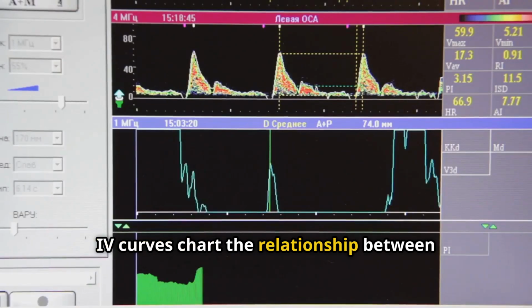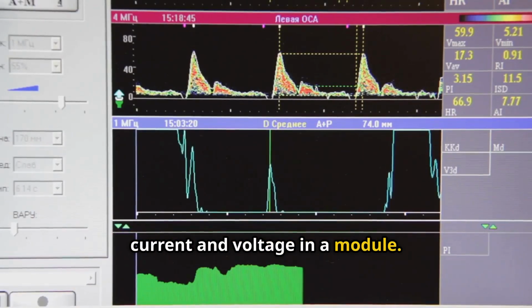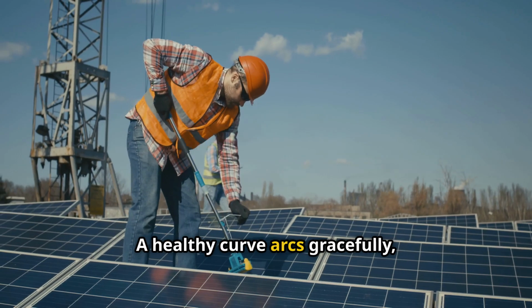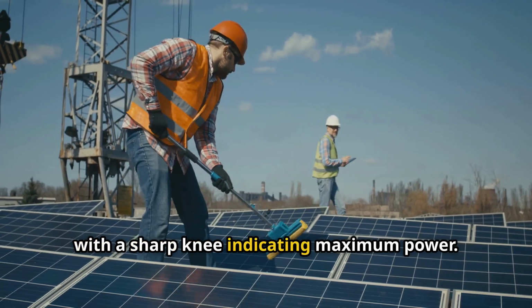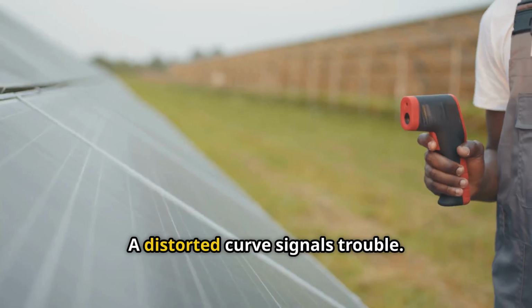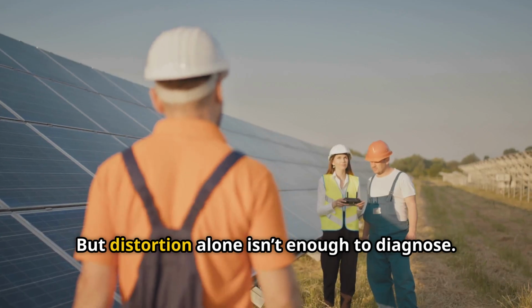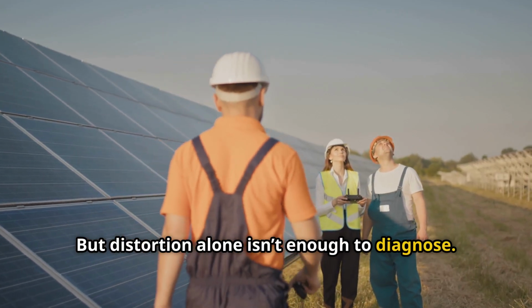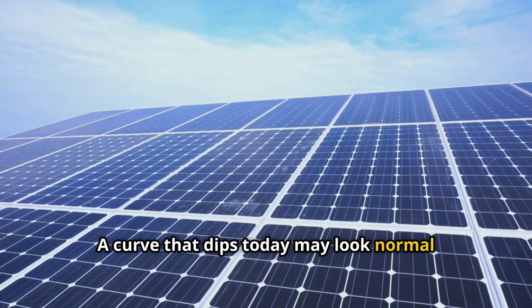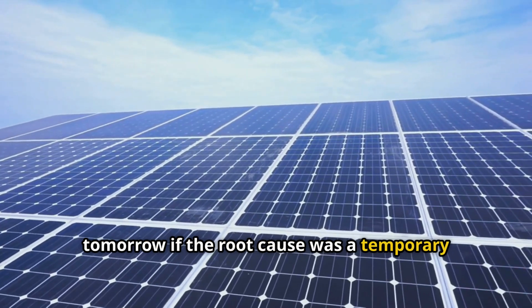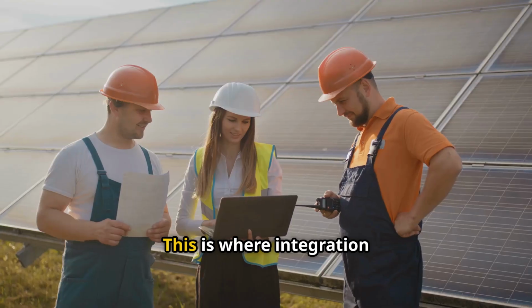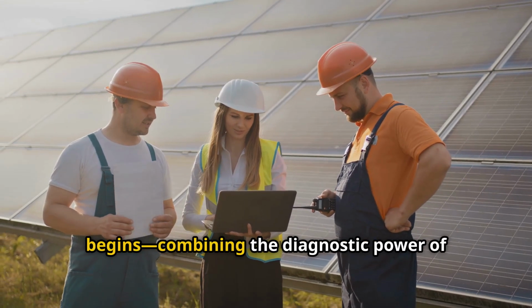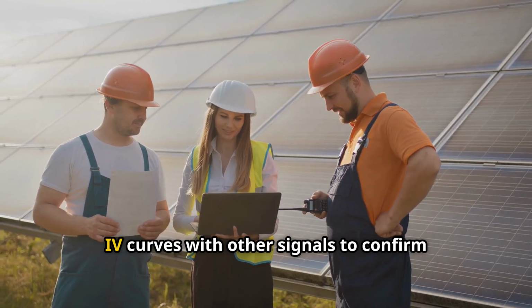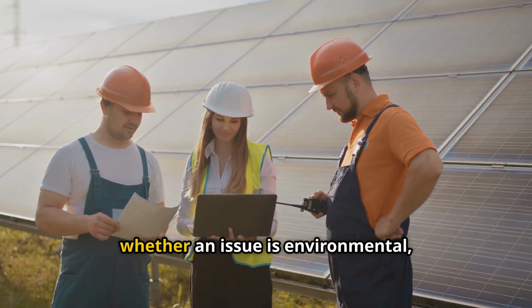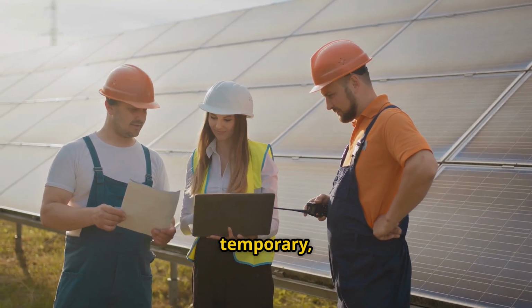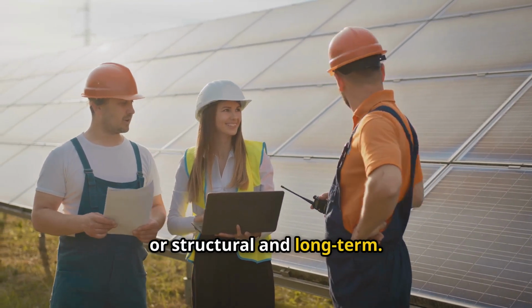IV curves chart the relationship between current and voltage in a module. A healthy curve arcs gracefully, with a sharp knee indicating maximum power. A distorted curve signals trouble, but distortion alone isn't enough to diagnose. A curve that dips today may look normal tomorrow if the root cause was a temporary shadow or high humidity. This is where integration begins, combining the diagnostic power of IV curves with other signals to confirm whether an issue is environmental, temporary, or structural and long-term.